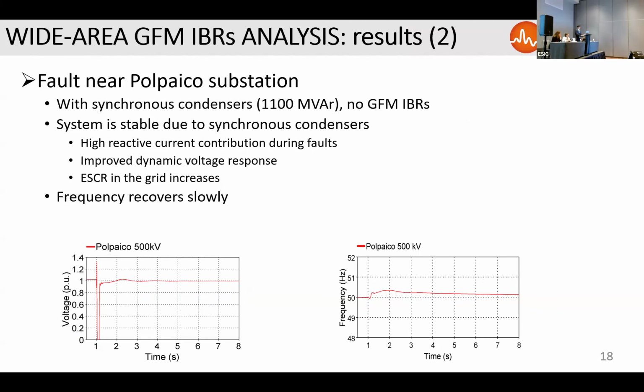So the corrective measure number one that was tested is to include synchronous condensers with a total power of 1100 megawatt. They are not using GFM converters at this point. They are installed in the same points that we were discussing previously, the points where the short circuit ratio is the lowest, so the most vulnerable points in the grid. The system becomes stable, as you can see in the graphs at the bottom. However, the frequency, despite being stable, is not necessarily at 50 hertz, which is the nominal in Chile, but slowly recovers after the fault clearance. But it's already better than before.